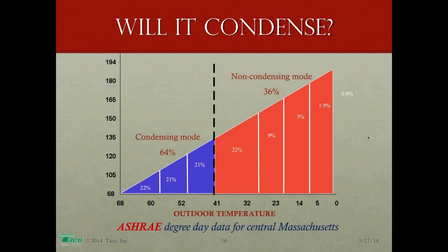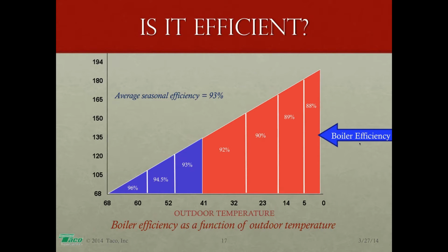That to me makes a very, very bold statement about how applicable a ModCon boiler would be in a fin tube baseboard retrofit application. I think that's kind of neat. Is it efficient? Well, yeah. Boiler efficiency is a function of outdoor temperature. Here we see the different relative efficiencies based on the return water temperatures going back to the boiler. And what we come up with here is an average seasonal efficiency of about 93%.